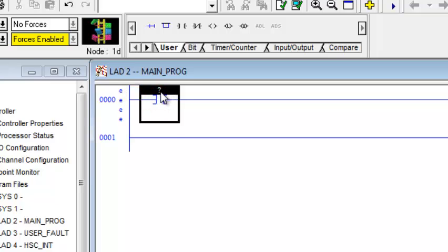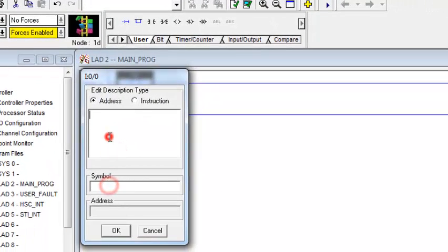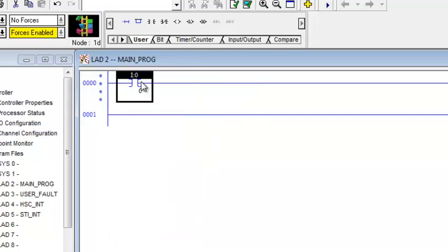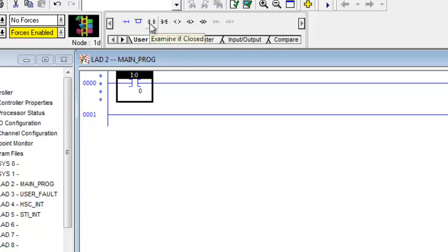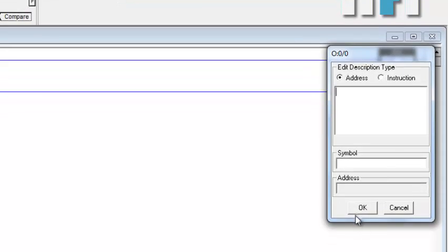Now we have to give it an address. Let's take the first input which is I colon zero slash zero. You can also add symbols and a description if you want. This bit will examine terminal I:0/0. Now let's add an output — pressing the output energized button — and entering address O colon zero slash zero.